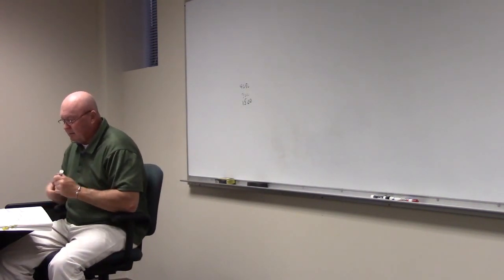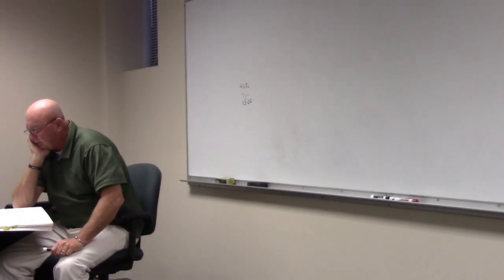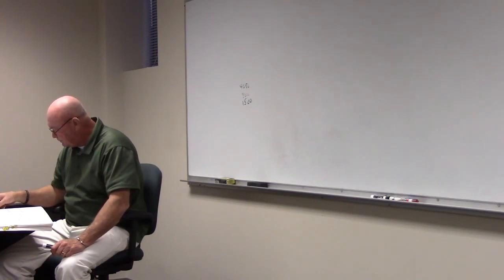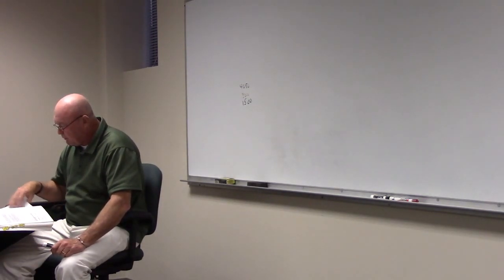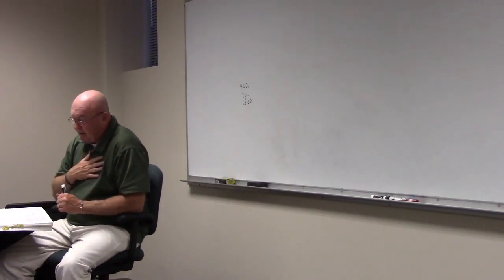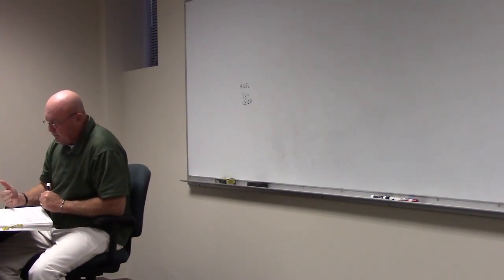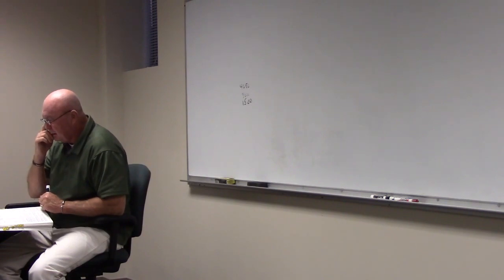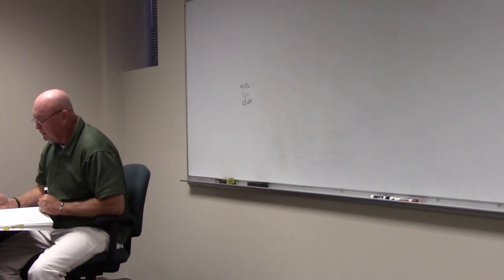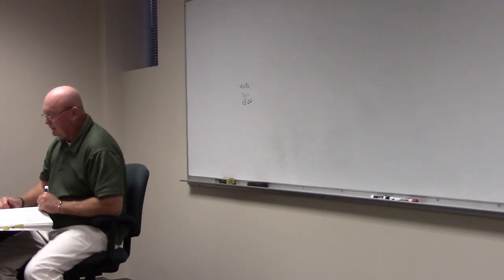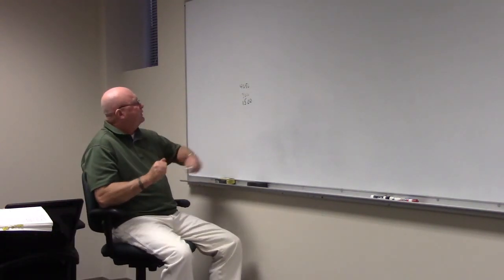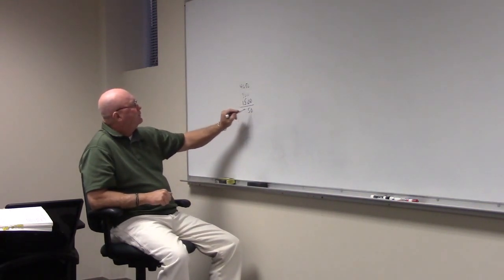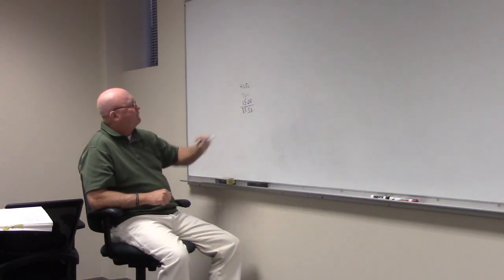Okay. So now step number 9 says to do this. Calculate the lighting load demand in the NEC 220.42. Note that the demand, let's go to 220.42. The table there says for a dwelling, the first 3,000 is what percentage? 100%. And the remainder is how much? 35. So let's figure out how much we got right now. We got what, 8,550.